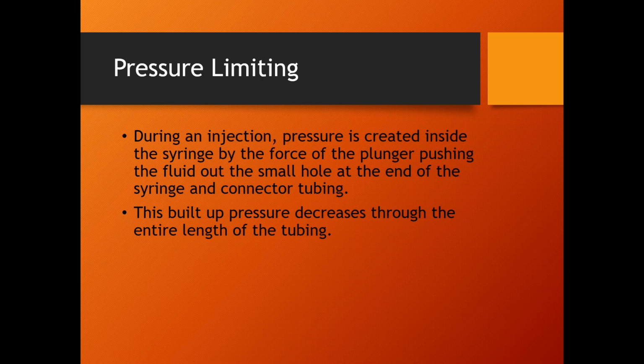Now that does matter for us as BMEDs, because when we're working on contrast injectors, you'll get a syringe, and you don't throw the syringe away after each injection. That's your PM syringe now. You're going to use it dozens and dozens of times for PMs. But eventually, someday, it will probably rupture when you're doing a pressure check. It's just the nature of it, it's just how it happens. When it happens, it'll happen while you're doing a PM in the room in the hospital. So you can literally turn around, say, "Can I have another syringe, please?" and carry on. All right, so that's what pressure limiting is.